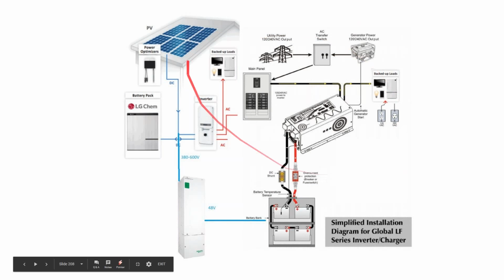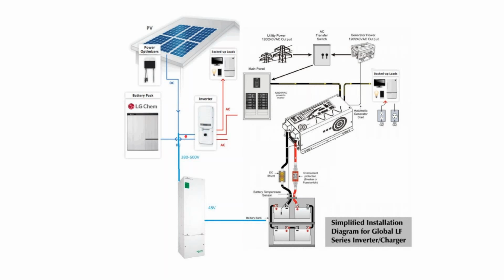Basically what we have here is an everything array: a flooded lead acid battery bank, a lithium-ion battery bank, a grid-tied lithium-ion battery inverter, and this would be on an automatic transfer switch on a generator interlock. So when the grid goes down, you flip it and you have your very cheap off-grid 120-240 battery inverter on its own battery bank, which could then go and turn on your batteryless solar inverter, or in this case, a battery inverter.